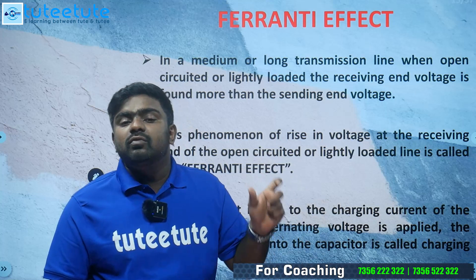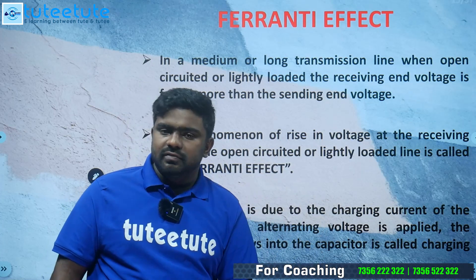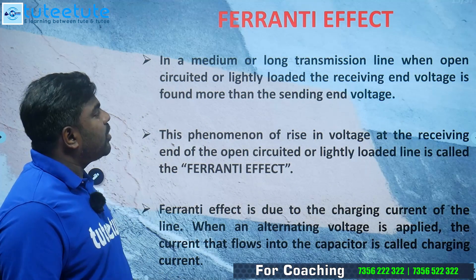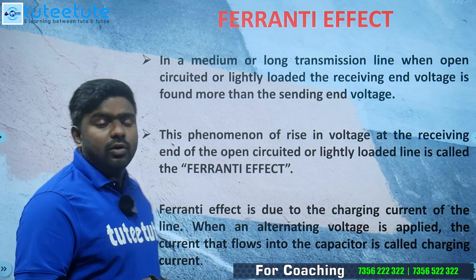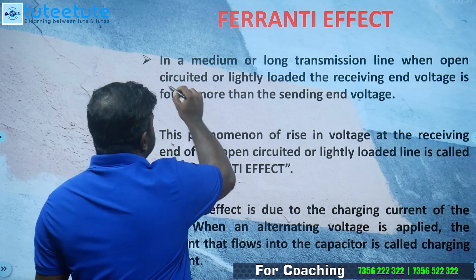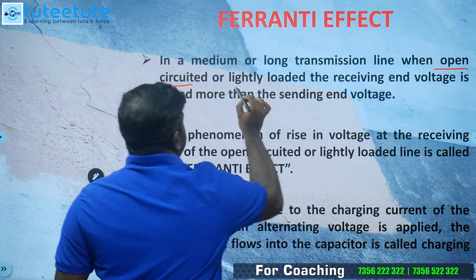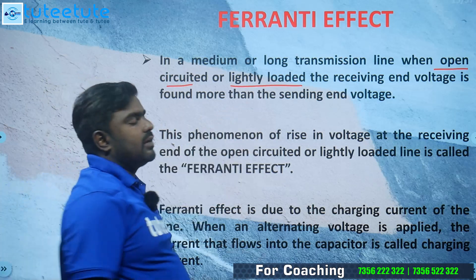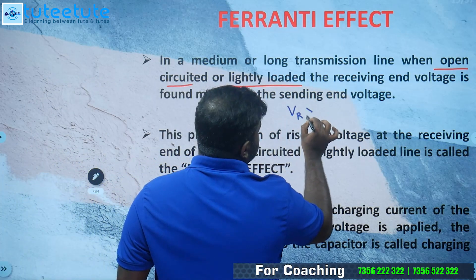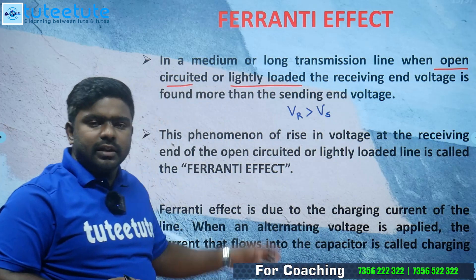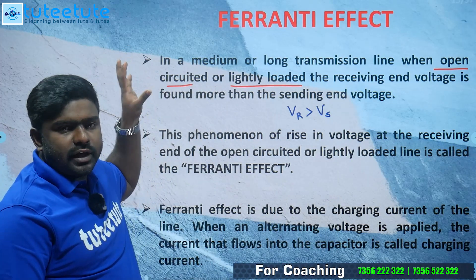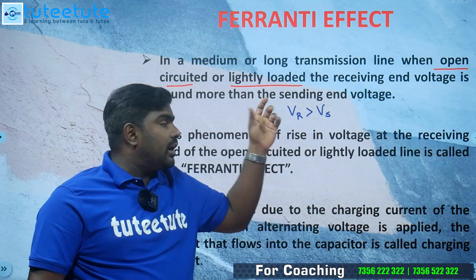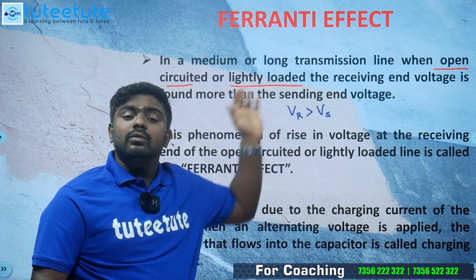In a medium or long transmission line, when open-circuited or lightly loaded, the receiving end voltage is found to be more than the sending end voltage — V receiving is greater than V sending. Usually the sending end voltage is dropped by the receiving end, but under lightly loaded or no-load conditions, the receiving end voltage exceeds the sending end.